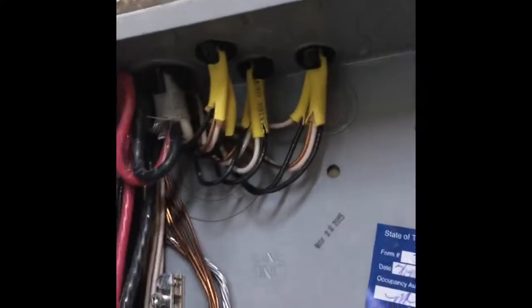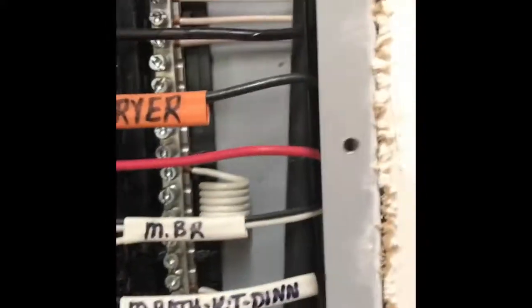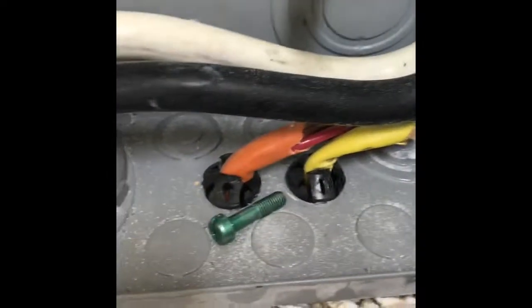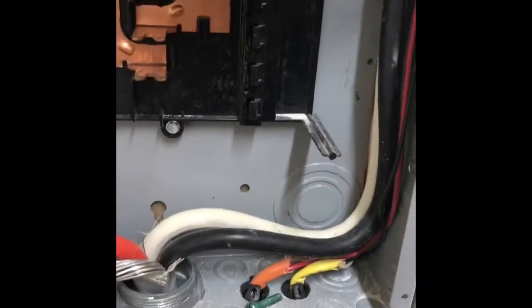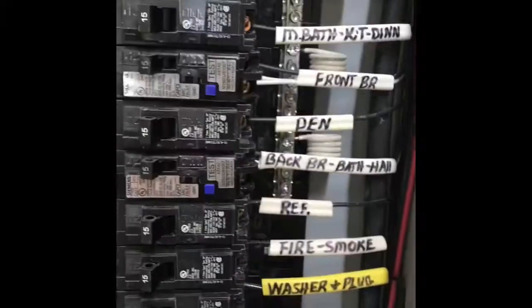It's clean, it's properly wired, they use proper paste, all the penetrations have proper bushings. This is a sub panel, the neutrals are all properly isolated. The grounds, the grounds are all properly isolated. The neutrals are all properly installed. The AFCI breaker neutral legs all properly installed. And they left the bonding screw behind just to prove that the neutrals and the grounds are separated. That's all I have for now.